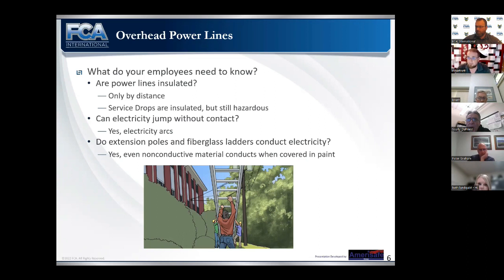And we also have to get rid of the fallacy that I'm safe because this does not conduct electricity. I've never seen any finishing contractor with tools that don't have some kind of dirt, paint, finish, splatter on them. And once you get some other material onto a non-conductive material, it becomes conductive. So when we're using aluminum ladders or when we're using fiberglass ladders, we need to make sure we take into consideration where the power lines are leading up to the job.